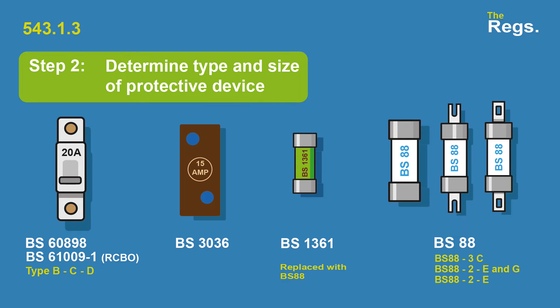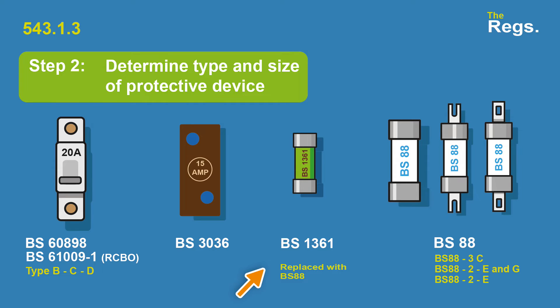Step two is to determine the type and size of the protective device. In our scenario we're using the BS88-3, but you've also got your BS60898 — your typical MCB — or your RCBO, your 61009, and various different types: B, C, and D. BS3036 is still recognised in the book. BS1361s are being replaced with the BS88s. So we've got a BS88 type 3.